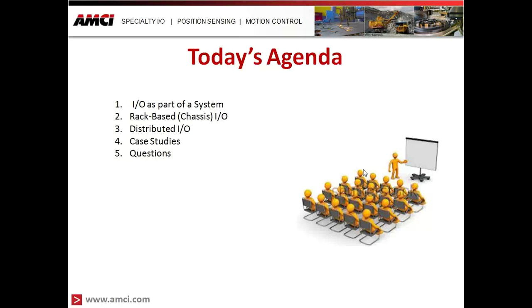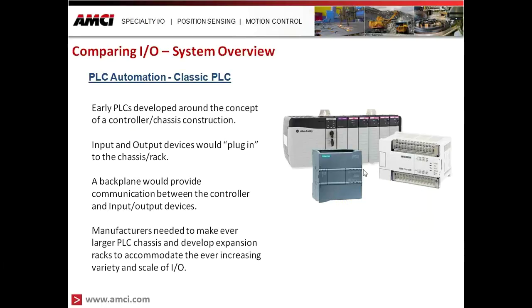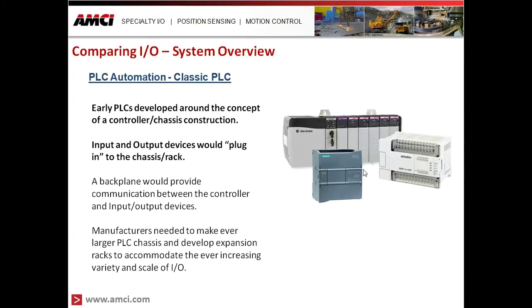When thinking about IO, we have to start with the PLC. In a classic PLC, we have both the chassis and controller construction. PLCs were developed back in the 70s around the controller and chassis as the main platform. In this setup, input and output devices would plug into that chassis or rack. If I needed DC inputs, I would add a DC input card; if I needed AC outputs, I would add an AC output card — just pick and choose what I needed.